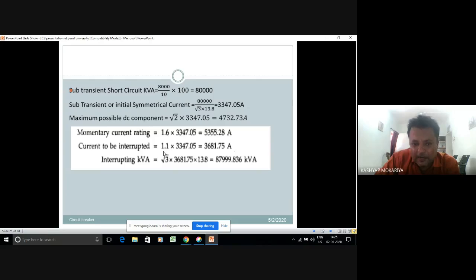Current to be interrupted is equal to 1.1 into 3347.05. So I'll get 3681.75 A. And now somebody tells you to find the capacity of the breaker in kVA or MVA. So I'll get the equation now: root 3 into the current to be interrupted, 3681.75, into your service voltage. And now you are coming to that for this type of specification of the breaker, you need an 87.99 MVA breaker, or perhaps an 88 MVA breaker.